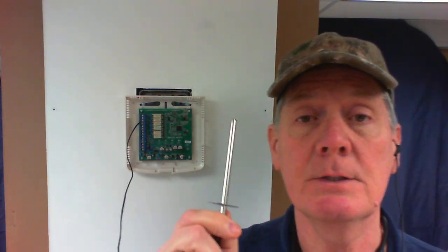In the event that we lose communication with the thermostat, then our control module that's connected to the HVAC equipment doesn't have any input. It doesn't know what the room temperature is, what your set point is, what mode you're in. It's lost all that input from the thermostat because we've lost our wireless connection. Could be the batteries went dead in the thermostat. Could be some radio interference issue. Any number of things can cause a communication loss. I have another video that discusses communication loss issues and common causes, so you can check out that video for more discussion about communication loss. But here we're just talking about this sensor.